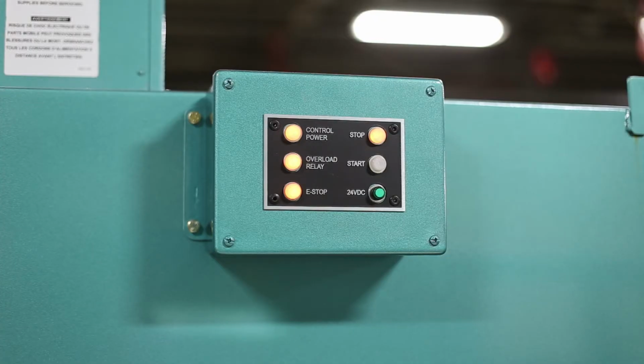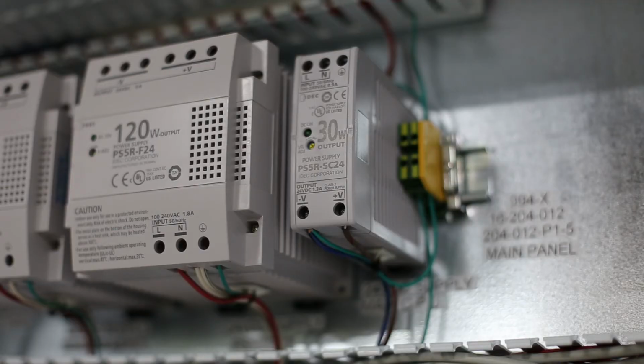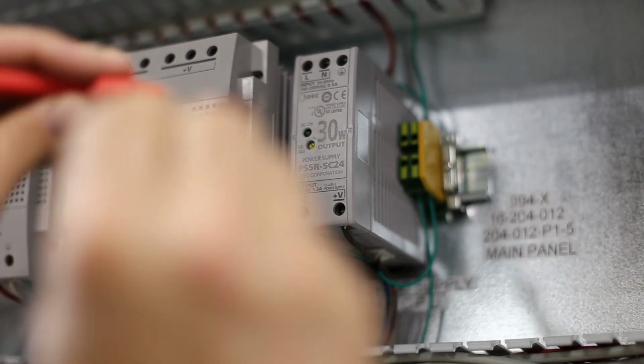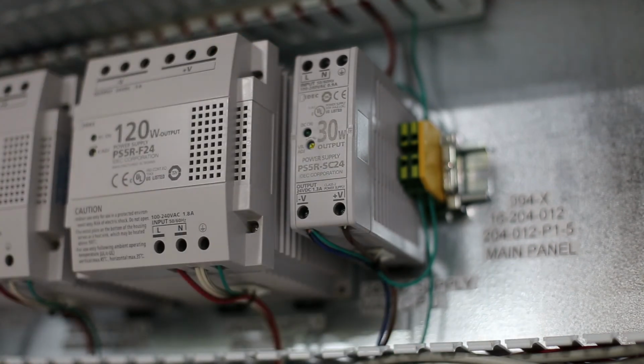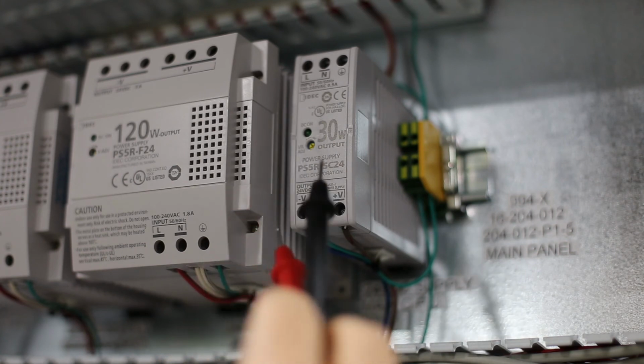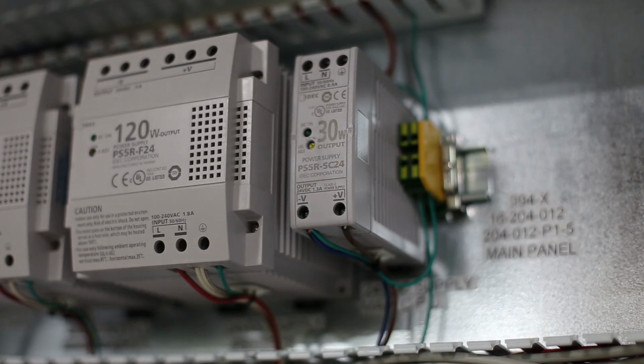Okay, now that we got our stop button on, the next thing we need to do is hit our start button. Now if the start light goes on when you hit the start button and it goes off as soon as you let go of the start button, that means our ACR relay is bad, or we need to see why it's not latching. What you want to do first is check up here at the very top between L and N for 120 volts AC. If you have 120 volts AC and this green light is out, that's your 24 volts saying it's off.